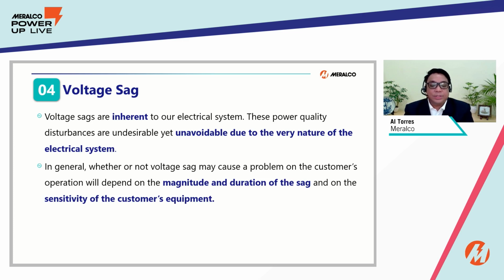We can say that voltage sags are inherent in our electrical system. These power quality disturbances are undesirable yet unavoidable due to the very nature of our electrical system. So, in general, whether or not a voltage sag may cause a problem on the customer's operation will depend on the magnitude and duration of the sag and on the sensitivity of the customer's equipment.